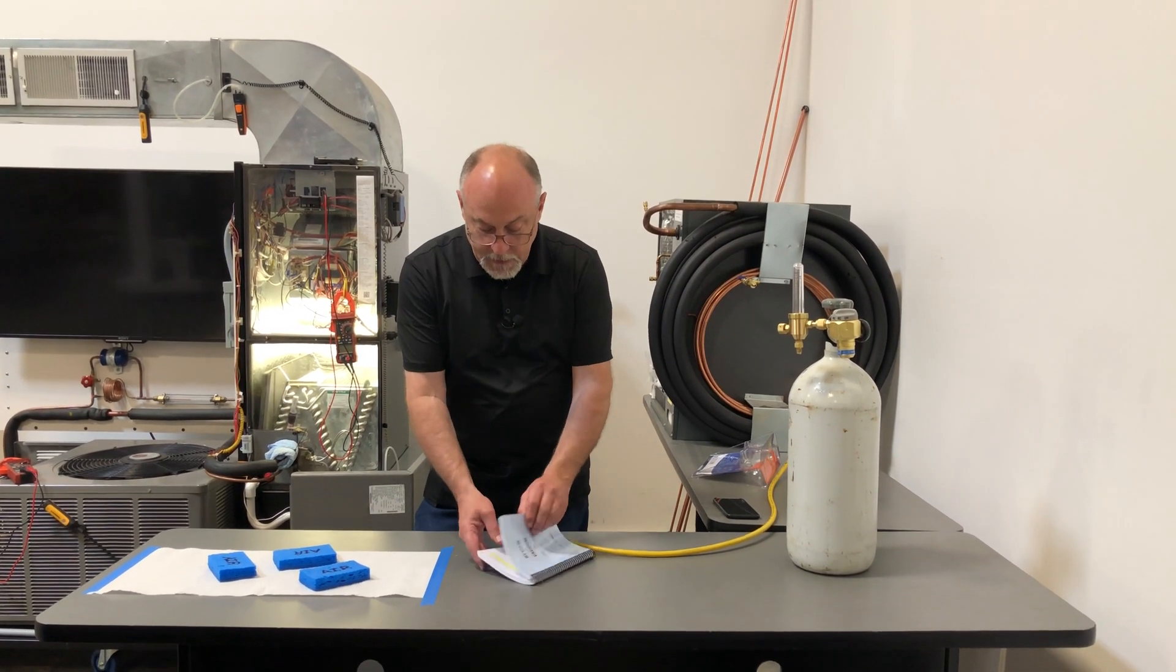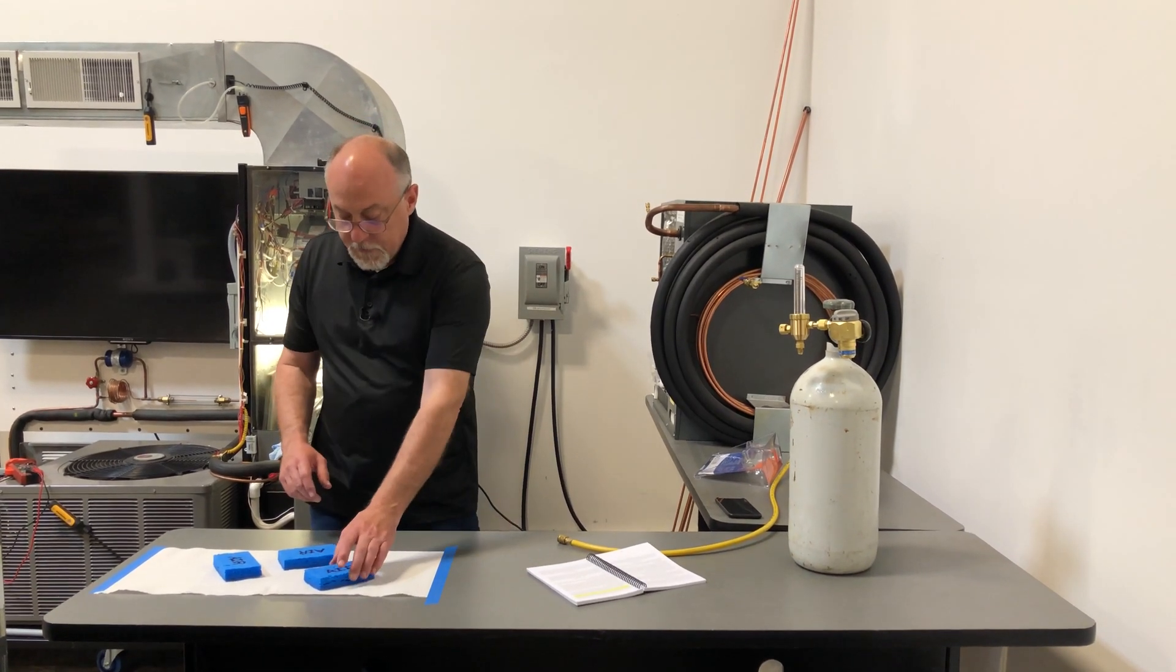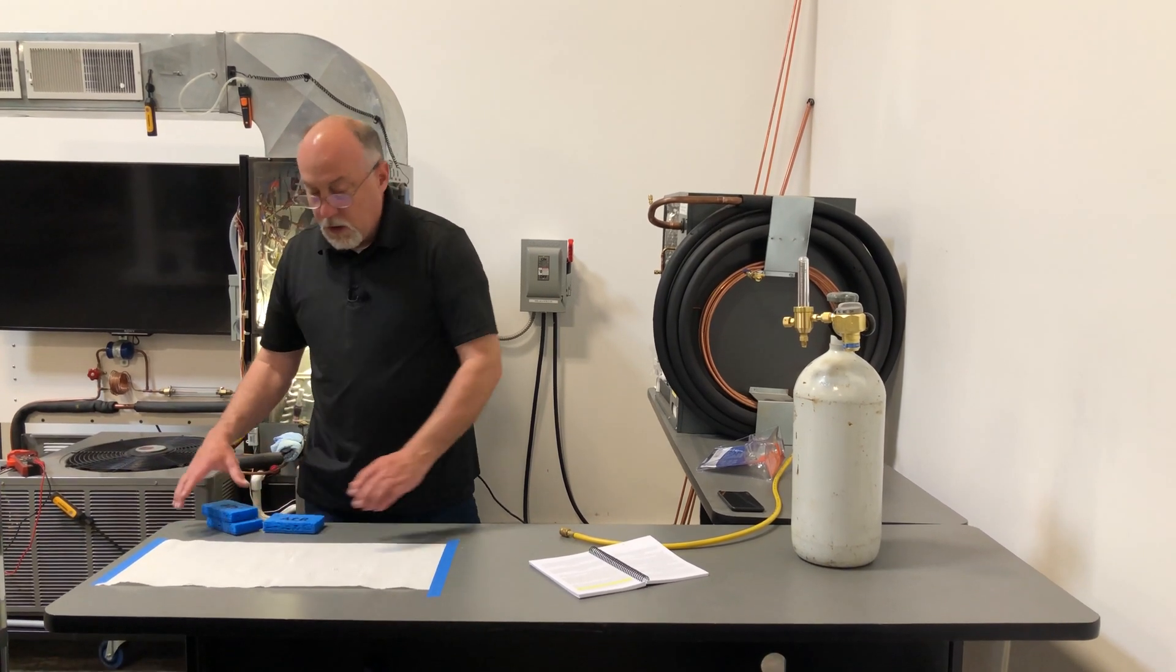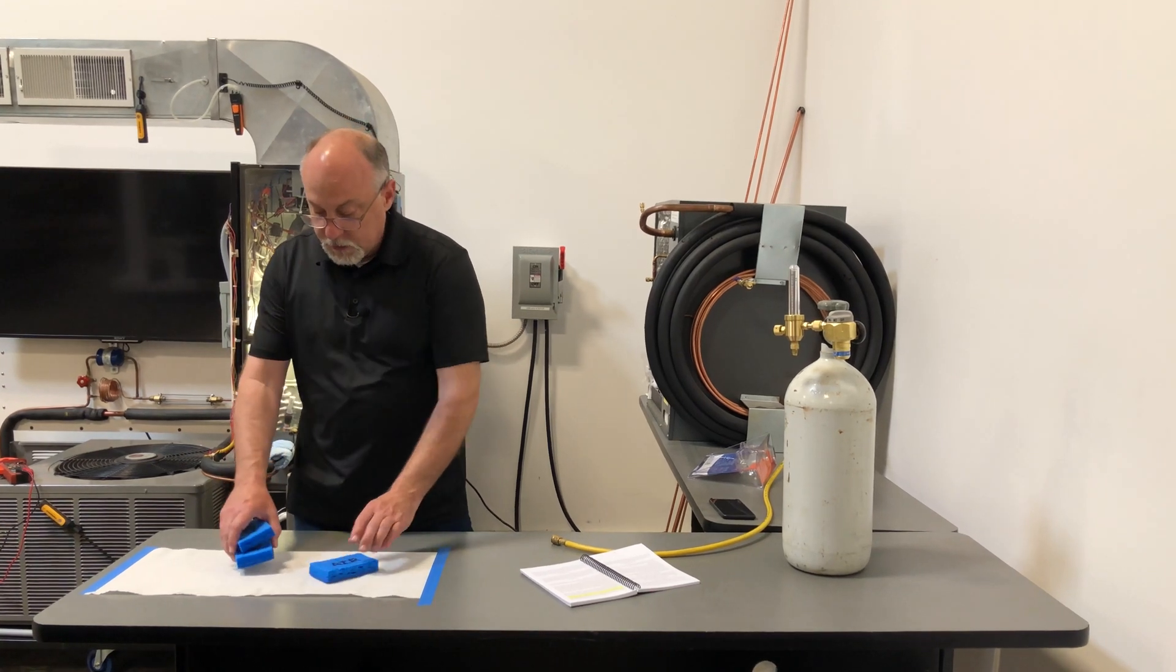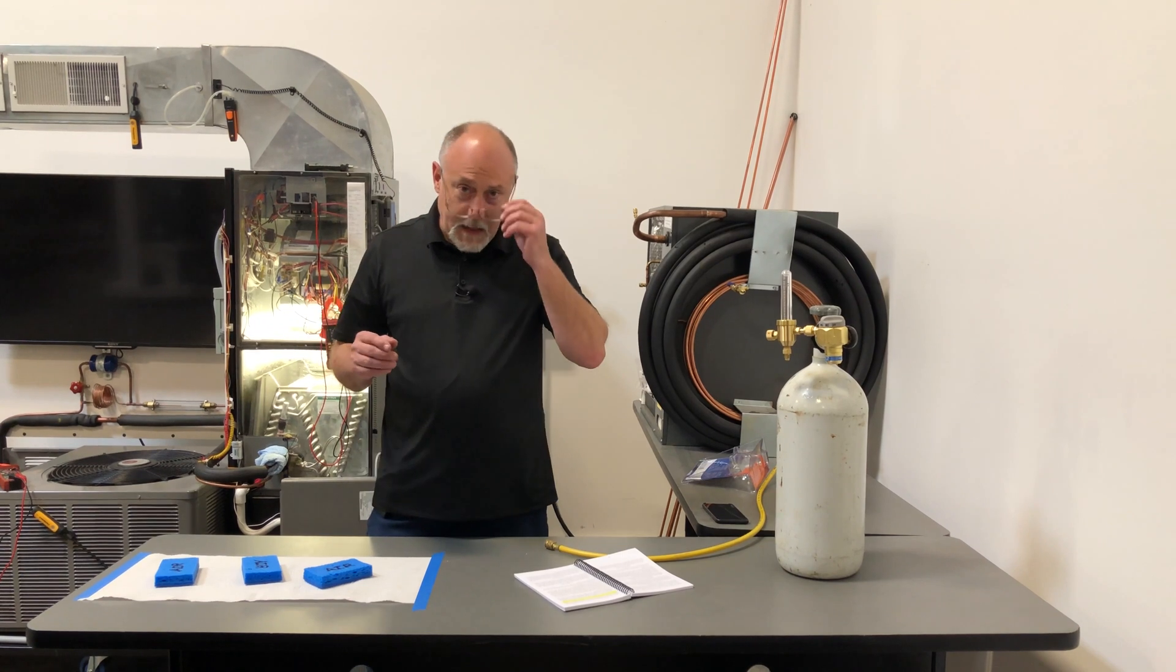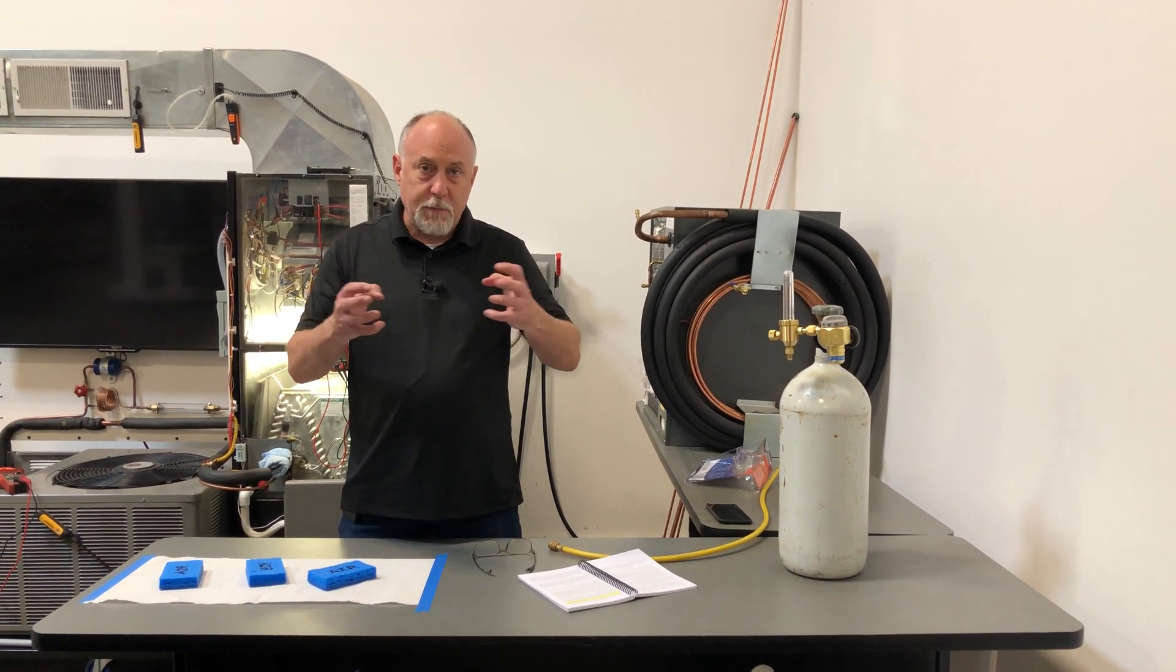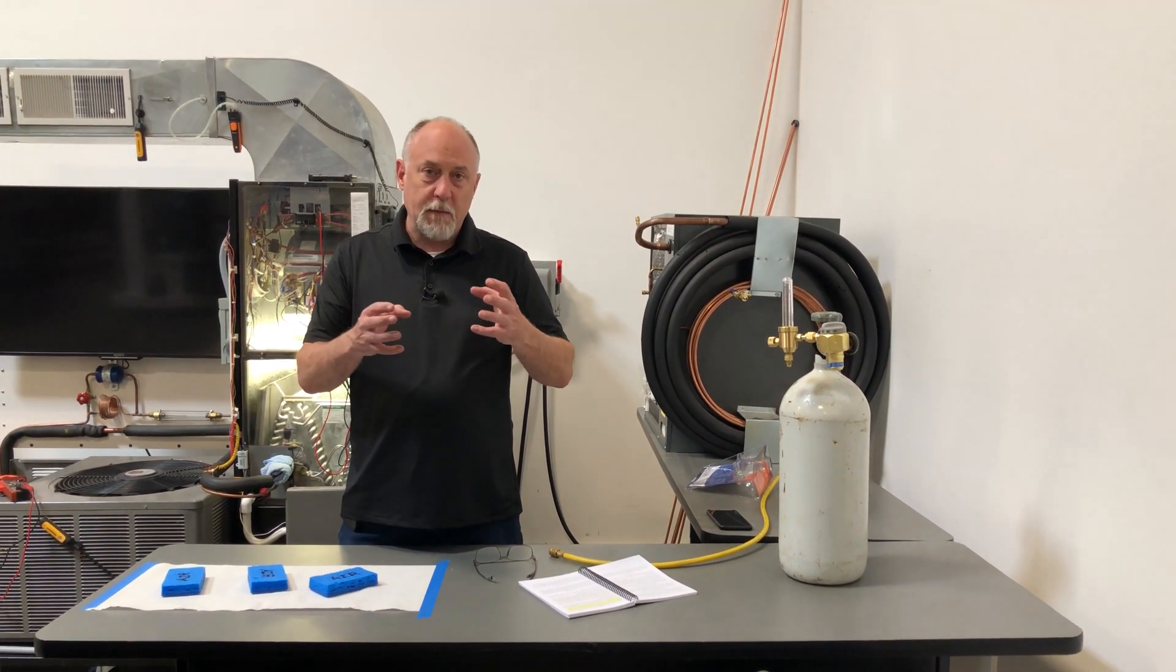We're talking about page 70, Review of Vacuum for Service Engineers. We want to take these air molecules and sweep them away. When we sweep the molecules away, even though there's some moisture in these sponges, these air molecules, it's all going to get swept away and carried down the system. It's not that nitrogen or oxygen in air is going to suck up the moisture, but moisture will reside in the open spots between the molecules.